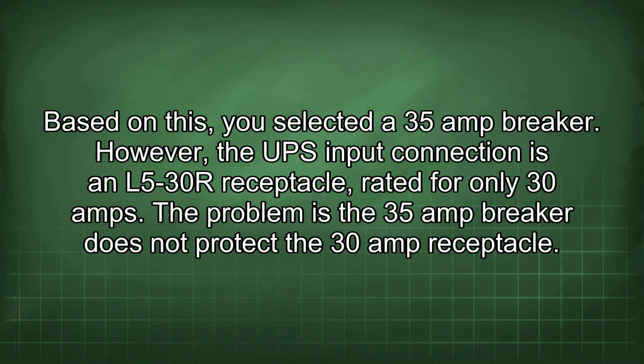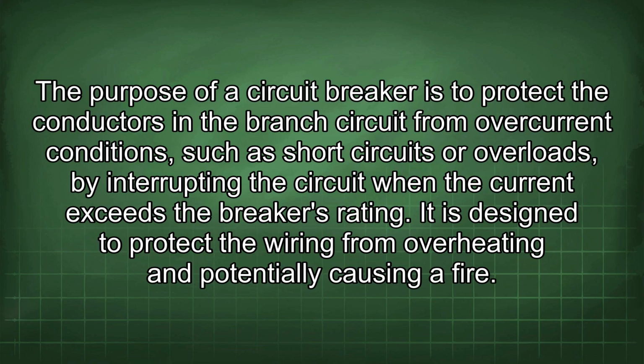However, the UPS input connection is an L5-30R receptacle rated for only 30 amps. The problem is the 35 amp breaker does not protect the 30 amp receptacle. The purpose of a circuit breaker is to protect the conductors in the branch circuit from overcurrent conditions such as short circuits or overloads by interrupting the circuit when the current exceeds the breaker's rating. It is designed to protect the wiring from overheating and potentially causing a fire.